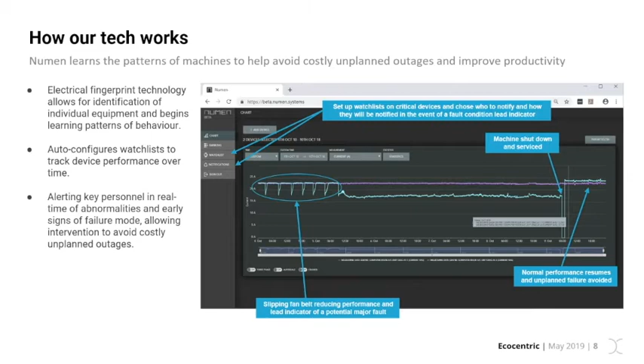These are the key elements of the Numen system. On the left, you can see the red, yellow, blue and black lines, representing the power lines into a building - 3 phases and neutral. The blue items that clip around the cables are current transformers, which detect the amperage of the current flow. They're designed by us with a few nifty little designs for electricians' ease of installation, etc. The Numen collector then takes the voltage references and the current references, and through those two parameters we can see an awful lot of data, mostly because of our sampling rate, which we'll get onto a bit later.